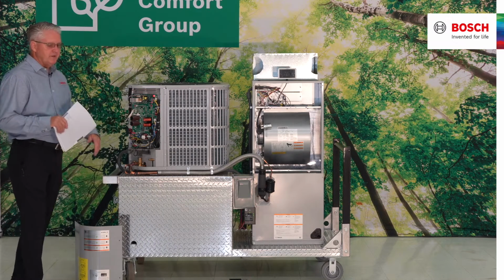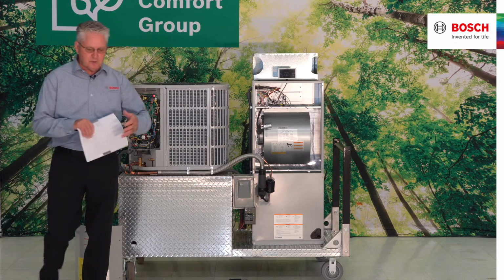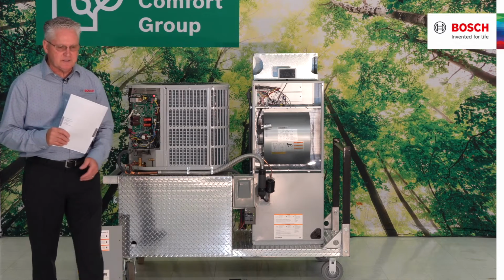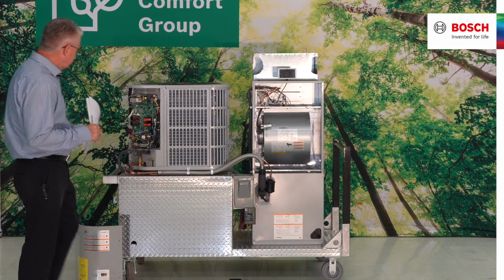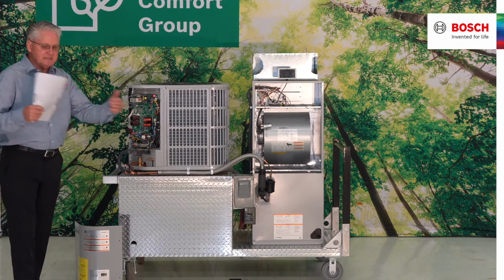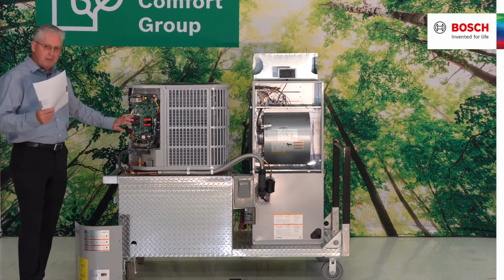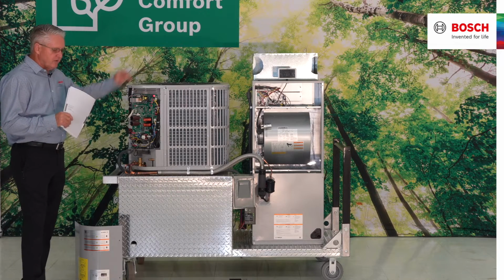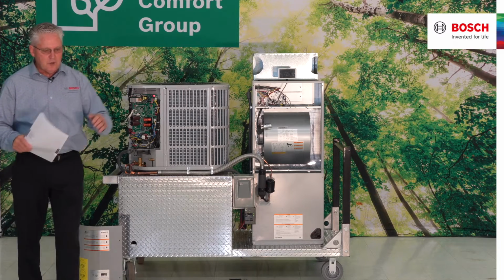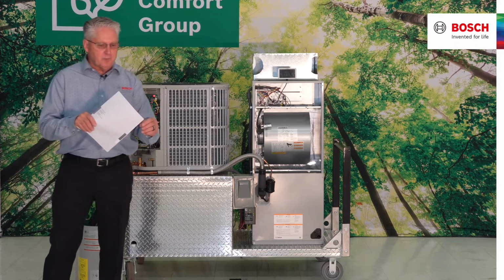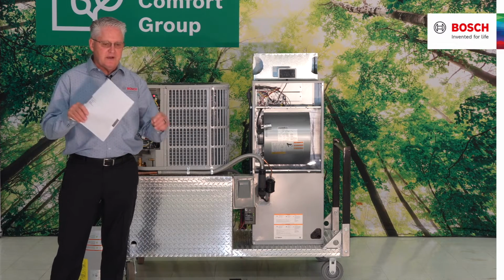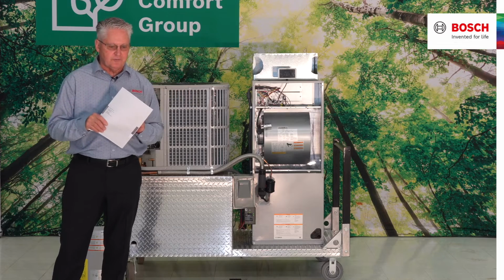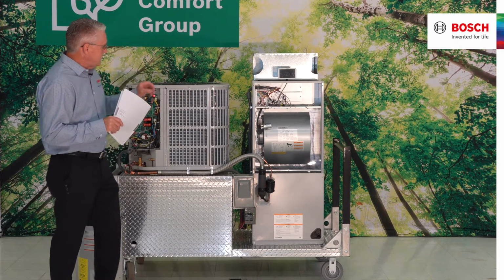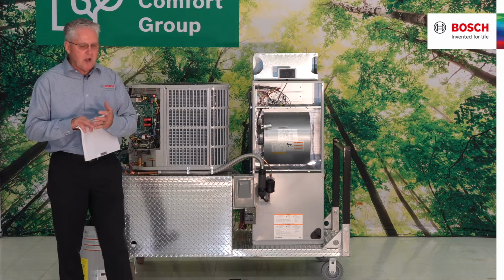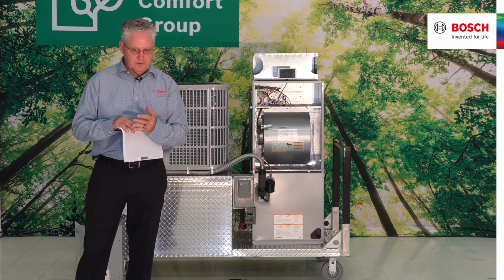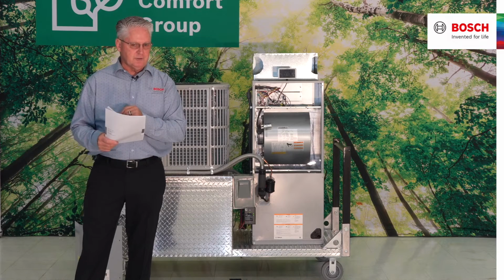This board is very familiar to you if you've seen the IDS 2.1, the 20 Seer, the 18 Seer. This particular board allows us to take the 240 volts and do the magic, if you don't mind, and have an inverter compressor that allows us to ramp up and down the compressor hertz rating, ramp up and down the capacity going to the indoor section, and to make sure that we keep a constant coil temperature via the pressure transducer.